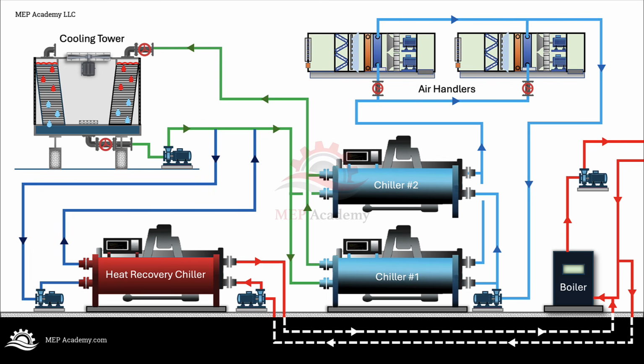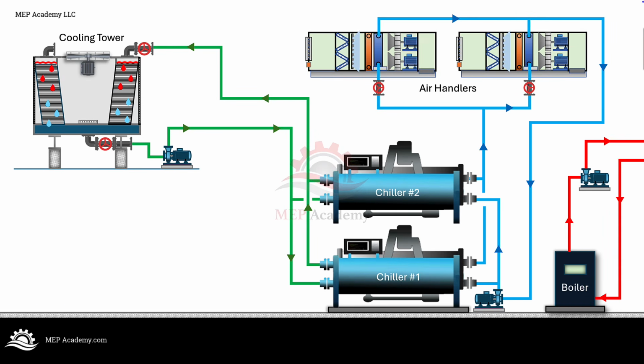With heat recovery, some of that heat can be captured and reused. This can reduce cooling tower load, reduce boiler load, and improve the overall efficiency of the plant. This first application is not just about one chiller. It is about optimizing the whole plant. The heat recovery chiller helps the main chillers by lowering the condenser water temperature, and it helps the heating system by providing recovered heat. Now let's look at a second application.